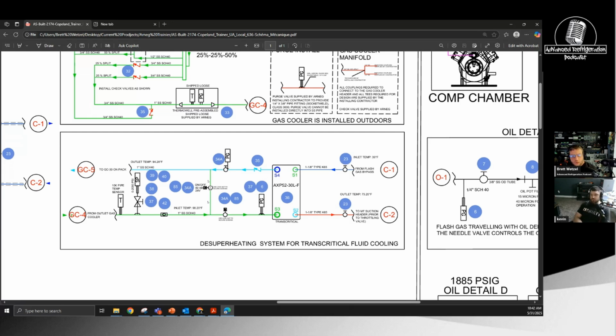So it's going to force gas through the heat exchanger, and then it's going to pick up cooling from the medium temp suction. But we had such a small system, and we had some superheat issues trying to get it to work, because it didn't have much. It's a trainer, so it's a stable load, but it didn't have enough to get me to lower the superheat enough to make it run properly, because it was so close -- the loads are literally on the rack, so there's no piping to pick up any superheat. So we ended up using this to get the medium temp suction to a proper temperature.